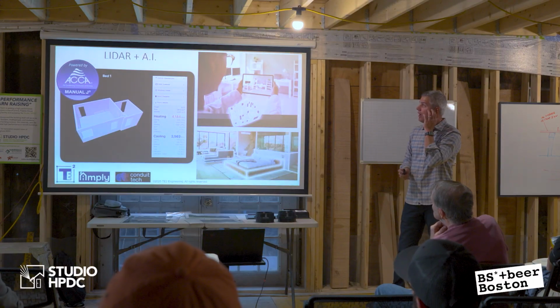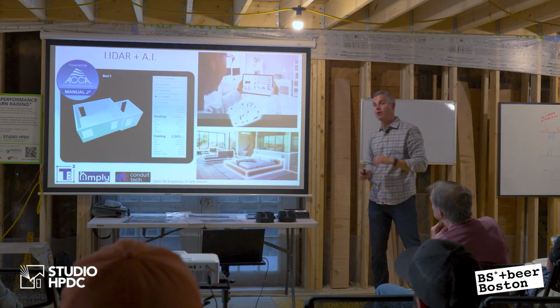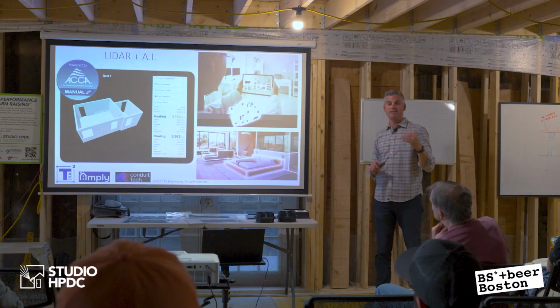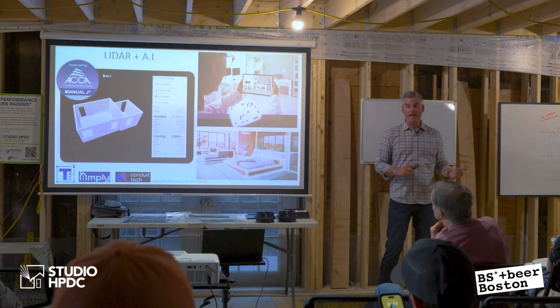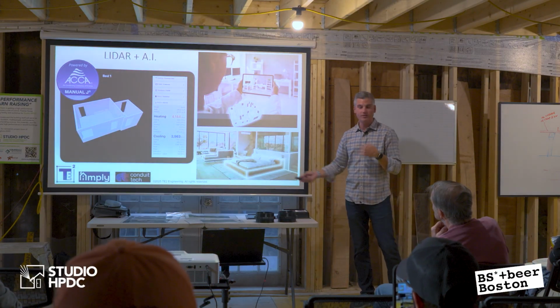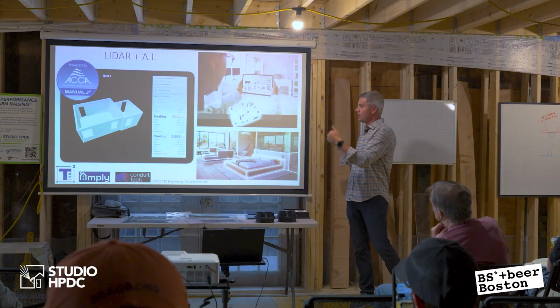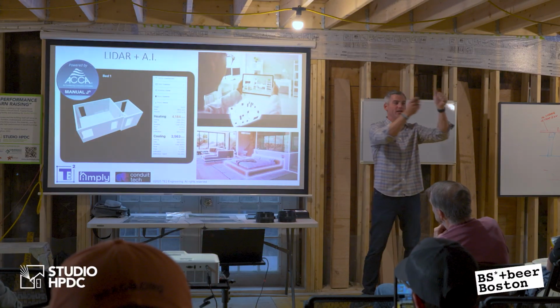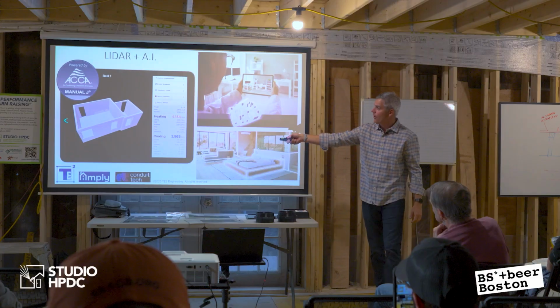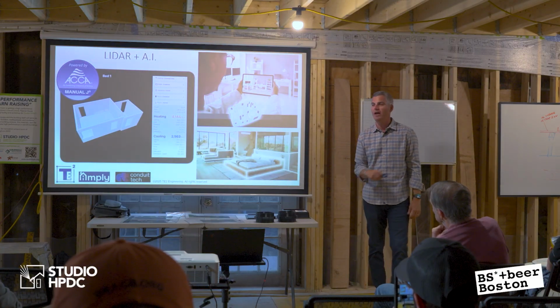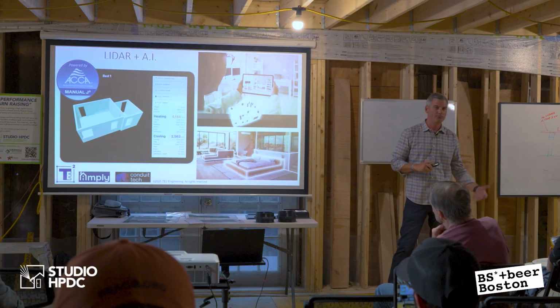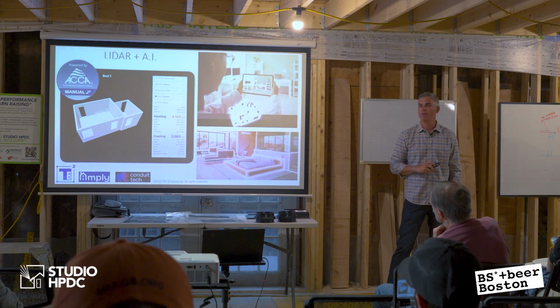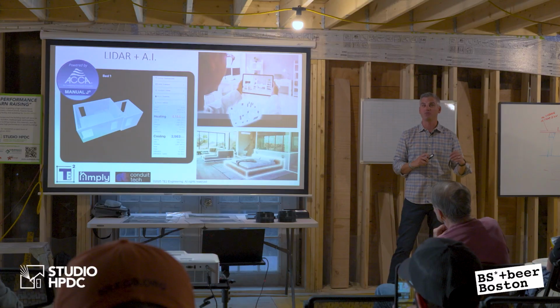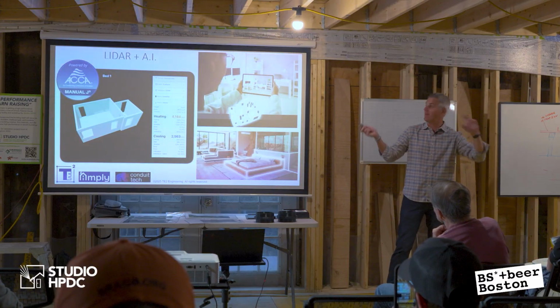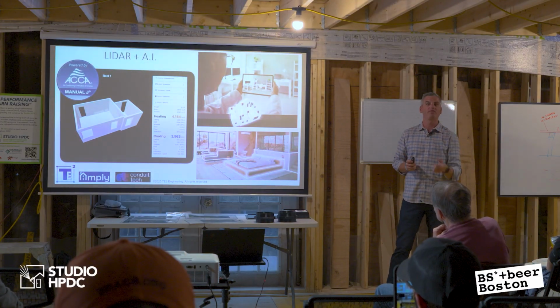We are starting to use a lot of AI and LiDAR in our business. And so if you're working on existing buildings and you want to do a Manual J, there are two companies, Amply and Conduit Tech, that I'm familiar with that we use, where you could take an iPad, you could scan the building, and it creates a 3D model of the space, and it gives you a Manual J in about probably 1/10 the time that it would take to normally do it. Does it work? Works amazing. We've done sensitivity studies. We've done it out the longhand way, and then in software, and then done it this way, and we're literally within 5% each time.